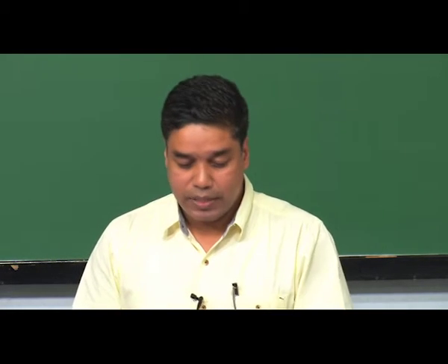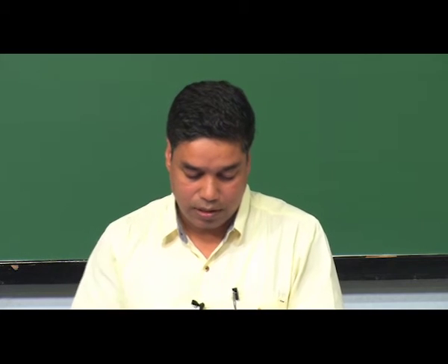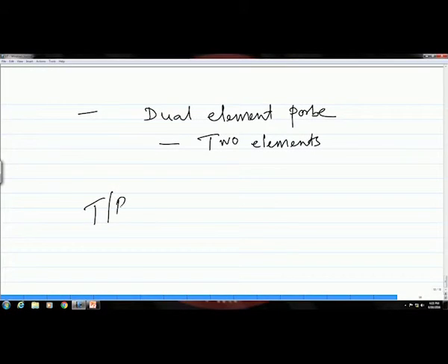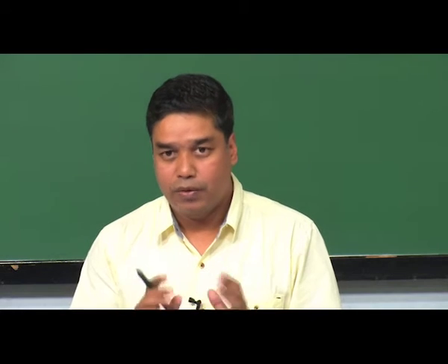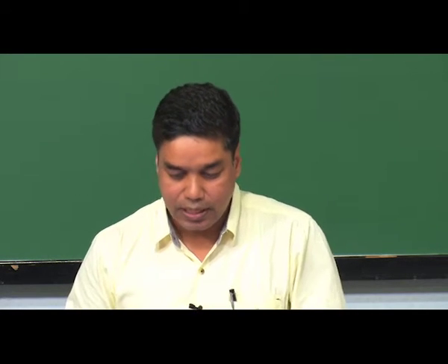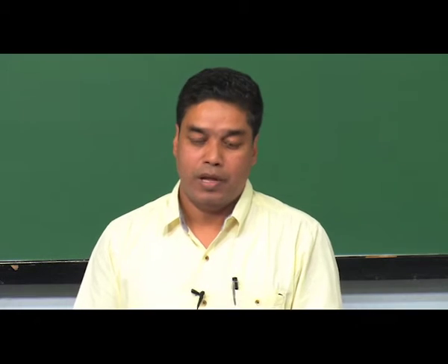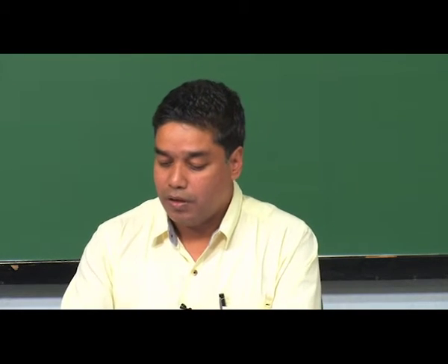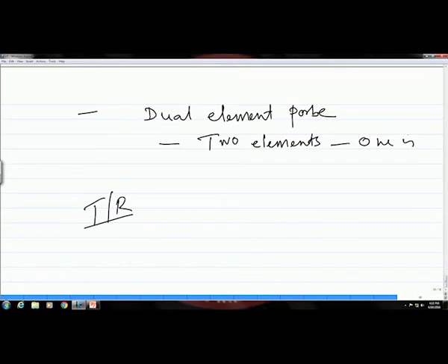So, in the rest of the cases that we discussed before, when you say that the same probe is used for both transmission and receiving, in those cases it is only one element, but in case of dual element probes, there are two elements. One is used as a transmitter, and the other is used as a receiver.